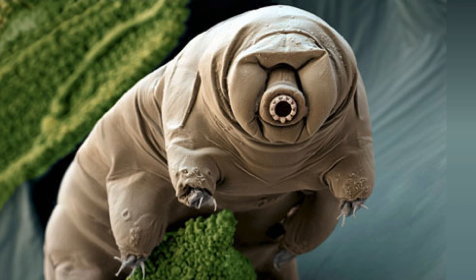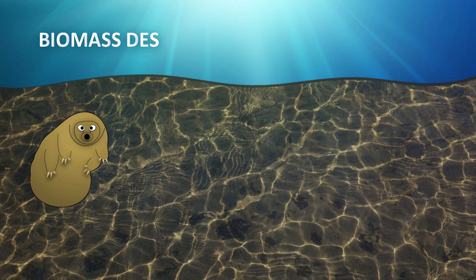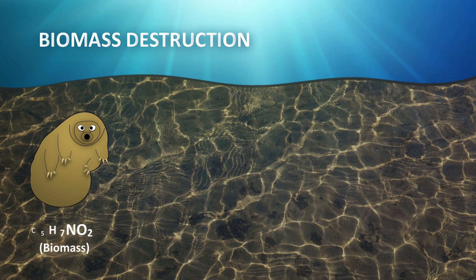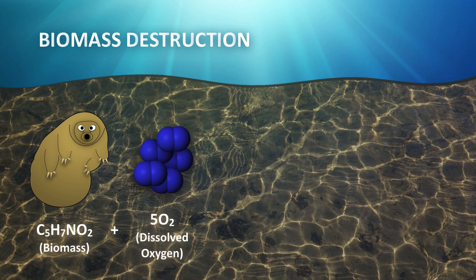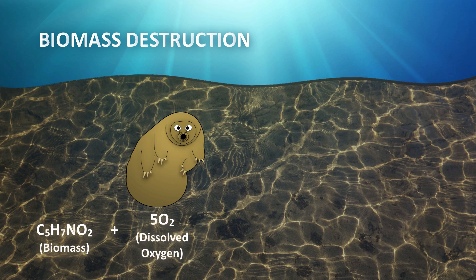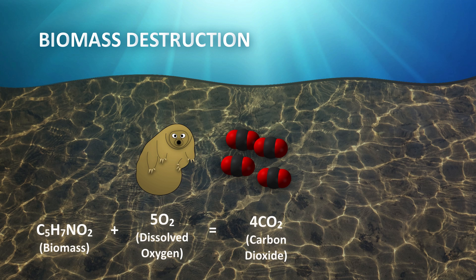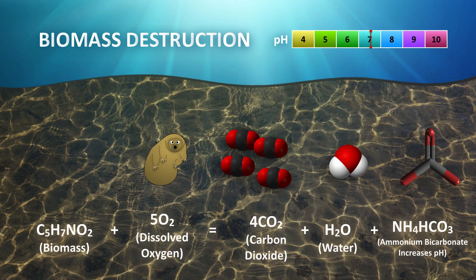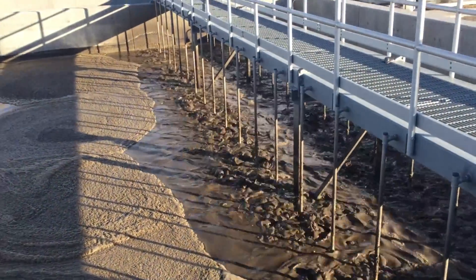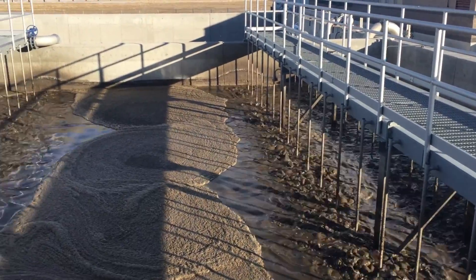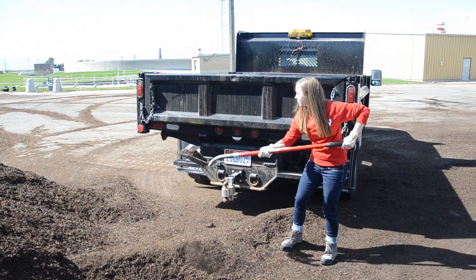The first biological process in an aerobic digestion system is biomass destruction. In biomass destruction, the food supply is depleted, so microorganisms consume their own protoplasm to obtain energy for cell maintenance reactions. The biomass requires 5 moles of oxygen to oxidize its own protoplasm, which is reduced to carbon dioxide, water, and ammonium bicarbonate. This describes how volatile solids reduction occurs. Essentially, under these conditions, the bugs will eat themselves, which means you need to haul less of them off.